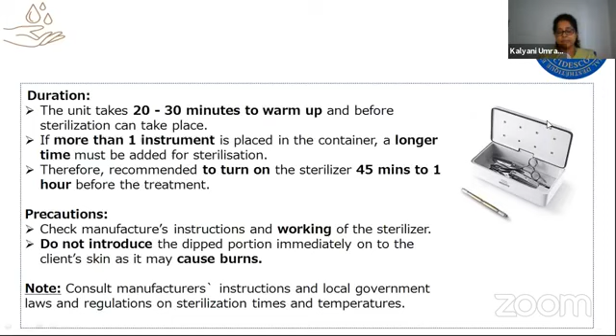Okay, then what is the temperature? The temperature at which the glass bead sterilizer operates is 300 degrees Celsius. Very high, very hot, like an oven. So don't try to touch the beads or the scissor or whatever you have dipped in with a naked hand. Your skin will come off. Yeah, please be careful. Now, it will sterilize the instrument in minutes. You won't have to keep it for very long, though you can keep it for say 10 to 15 minutes. Now, ideally, you have to again read the manufacturer's instructions. That's the best part.